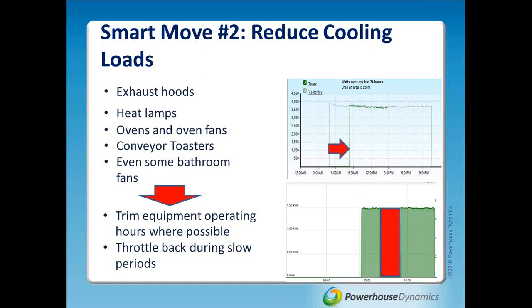One interesting thing to think about is a human at rest adds about 450 BTUs of heat to any given room. So as your guests increase, they themselves are generating cooling load. But a conveyor toaster is usually between 1,000 and 3,000 watts. For an hour, that is about 3,500 BTUs. So the question you might ask yourself is, how many extra guests do you have standing in your kitchen? Probably a lot, of equipment that's operating, generating heat. Of course, you have to have some to do your core business, but the point here is making seasonal adjustments to your business is probably not something new. Menus change, other things change, and some of these operating procedures can change to your benefit when it comes to reducing your cooling loads during the summer.